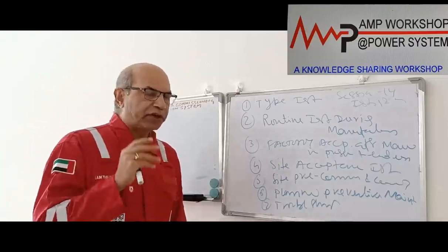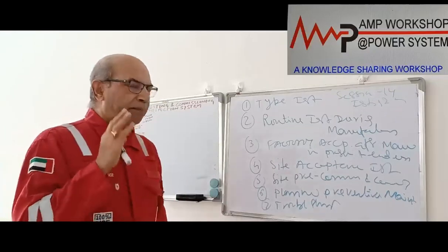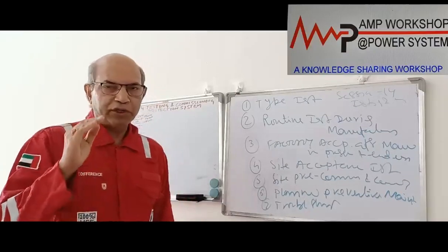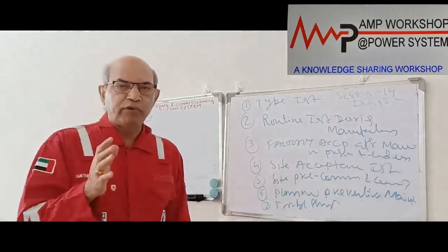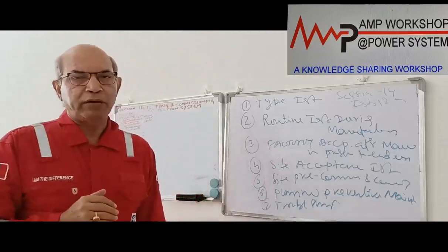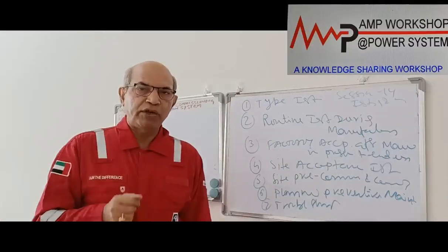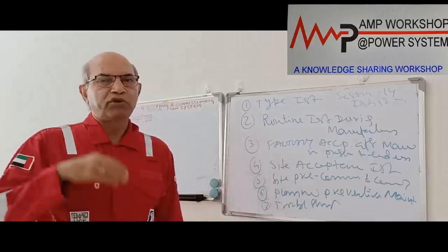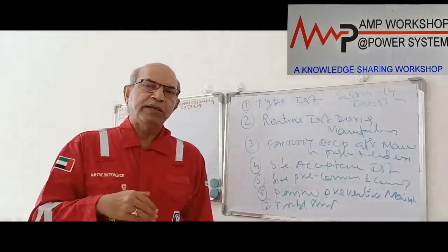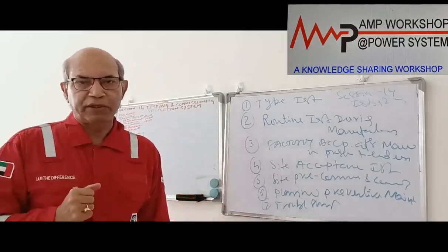Now, in the case of a protection relay, we do various type tests. Why do we do them? By these type tests, the protection relay's performance is proved, meaning it does not maloperate under various influences. Various abnormal conditions can be created in the power system, like a switching operation. When you do the switching operation, a switching surge is created in the power system. If there is a lightning impulse injected on the line, then a lot of disturbance comes in the line.